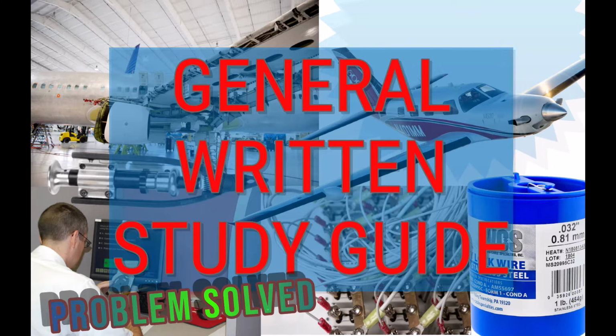The end of charge voltage of a 19-cell NiCad battery measured while still on charge depends upon its temperature and the method used for charging. NiCad batteries, which are stored for a long period of time, will show a low liquid level because electrolyte becomes absorbed into the plates. How can the state of charge of a nickel-cadmium battery be determined? By a measured discharge. What may result if water is added to a NiCad battery when it is not fully charged? Excessive spewing is likely to occur during the charging cycle.